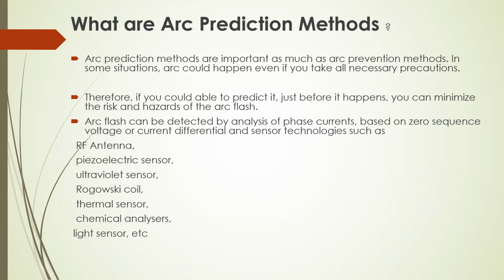What are the arc prediction methods? Arc prediction methods are as important as arc prevention methods. In some situations, arc could happen even if you take all necessary precautions. Therefore, if you are able to predict it just before it happens, you can minimize the risk and hazards of arc flash. Arc flash can be detected by analysis of phase currents based on the zero sequence voltage or current differential, and sensor technologies such as RF antenna, piezoelectric sensor, ultraviolet sensor, Rogowski coil, thermal sensor, chemical analyzers, light sensor, etc.